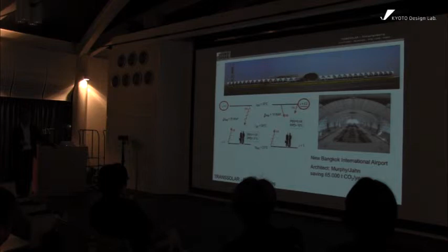After the first design step, they found the building needed too much energy. There was also a second problem: a lot of condensation outside the building, because the outside temperature is nearly 30 degrees with 90% humidity. So if you reduce the inside temperature to 24 degrees, you get condensation outside on the single layer membrane and glass.